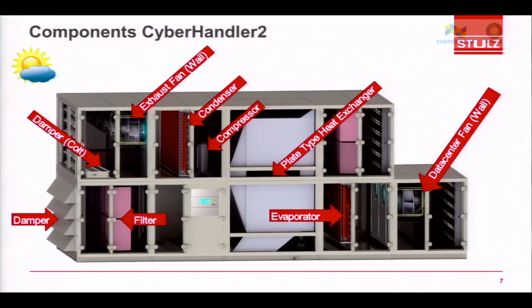Here are the components. We have a damper, filter, and again our beloved EC fan; I feel from day one we have been using EC fans. EC fans are going to help us in exhaust as well as supply. We have to use a plate type heat exchanger, an air to air heat exchanger, in the air handling unit. Again filtration, again a cooling system, but don't use the cooling system for cooling the data center. Use free cooling and adiabatic cooling, and I will cover how it is going to improve the PUE of the data center.